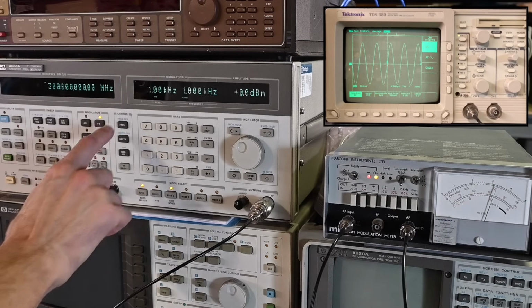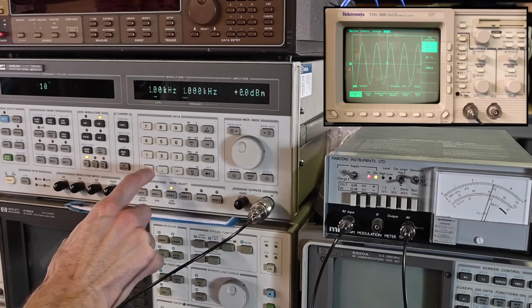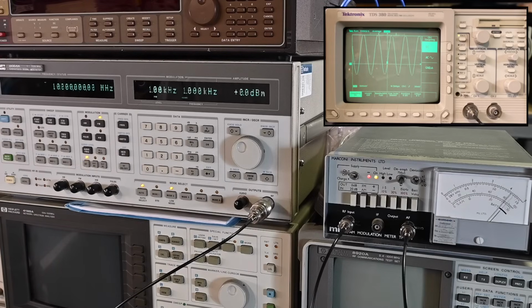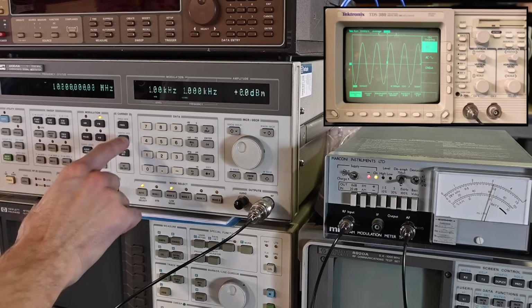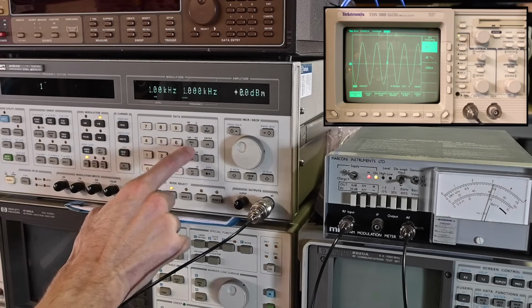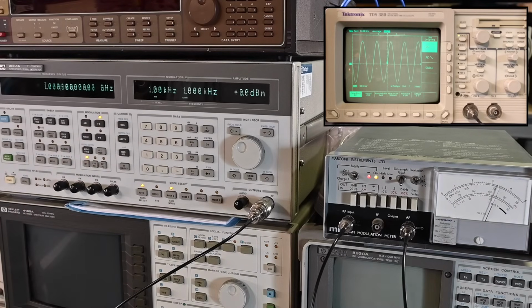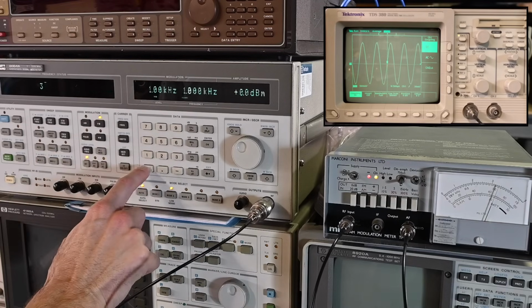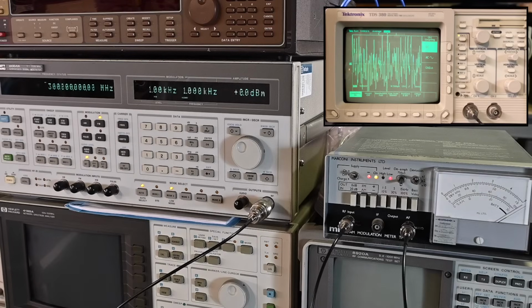Now if I go over here to the frequency and change this, let's go all the way down to, let's say, 10 megahertz. And there it goes. It locked back on and is working correctly. You can see on the oscilloscope, no problems there. And let's go back up to, say, all the way to 1 gigahertz. There you go. The top end of the range, no problems. I'll just put this back to 300 megahertz. It's perfectly fine. I'll just leave it on 300 megahertz for the rest of the test.